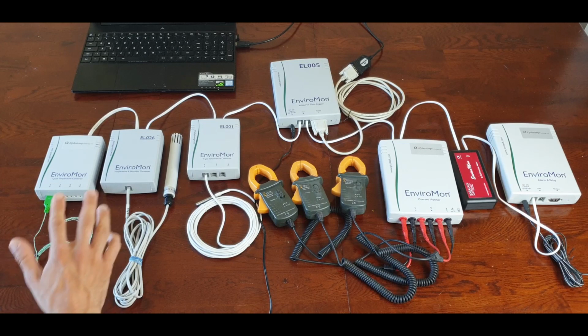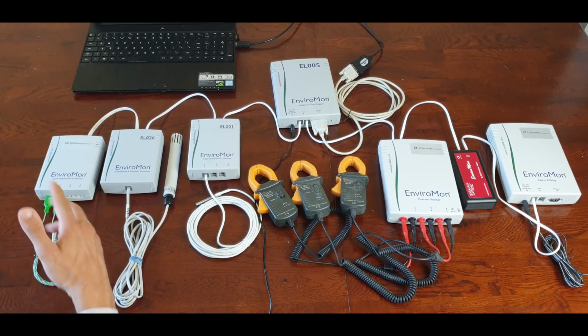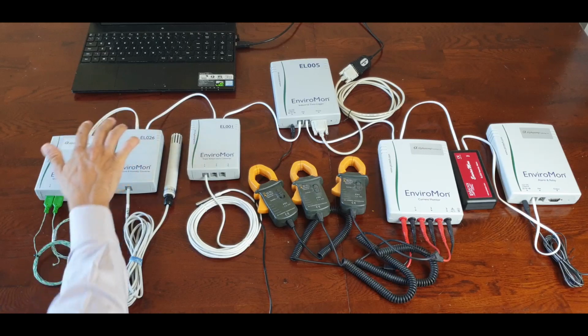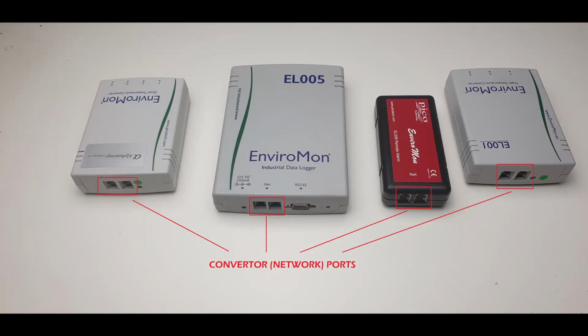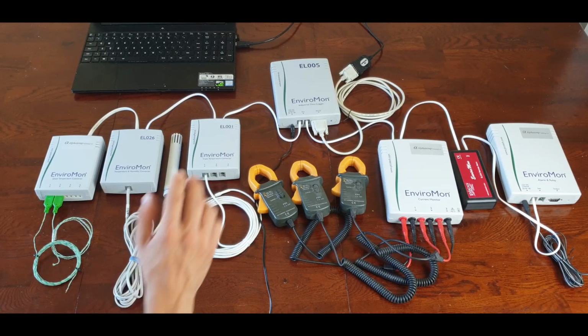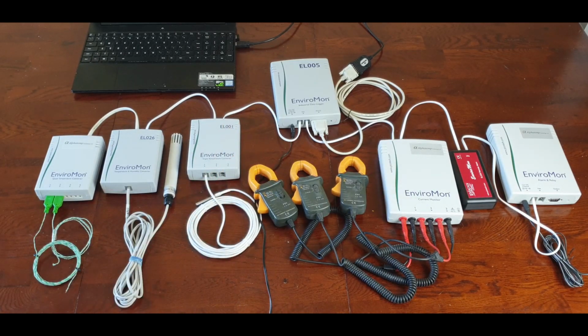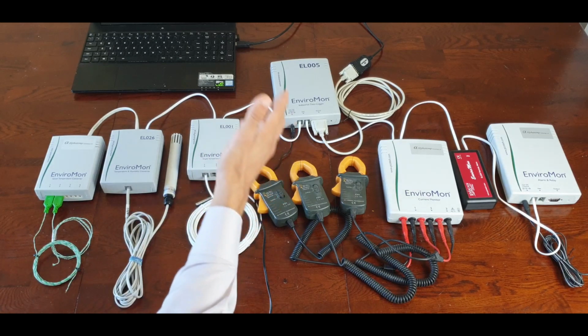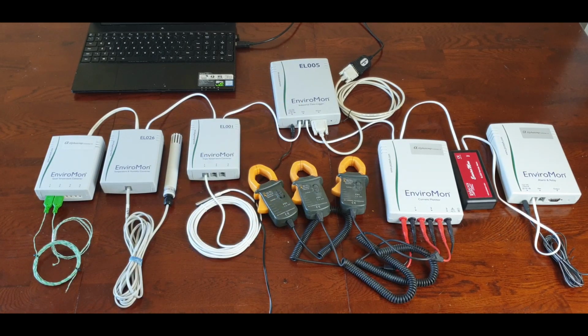Now, they're connected to each other and to the data logger using a network cable, or as I prefer the name, converter cable. And as you can see at the back of each of these units, or on the data logger or the alarm unit, they each have two network ports, or as I call them, converter ports. Now, the logger itself requires power, and it's connected to the PC using a serial adapter or a USB to serial interface for initial configuration on your computer. After that, it can be disconnected from the computer and later connected to download the data, or you can optionally have it remain connected to the PC at all times to get the most up-to-date readings downloaded and stored.